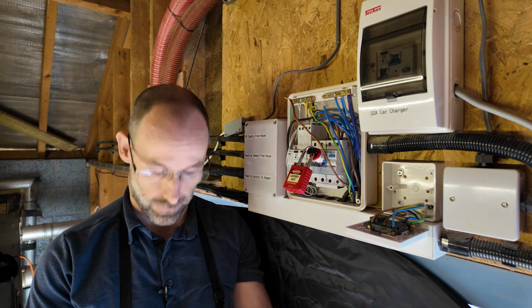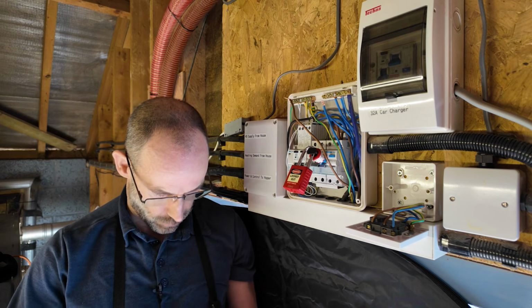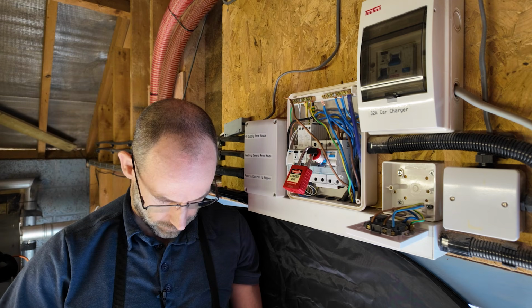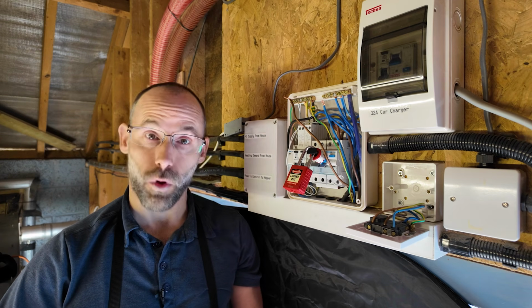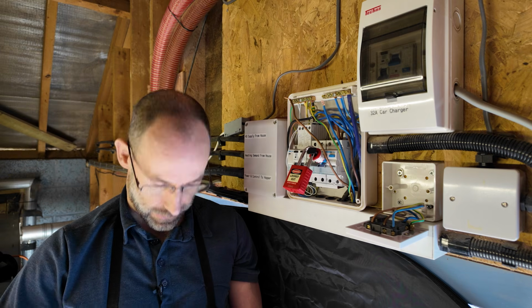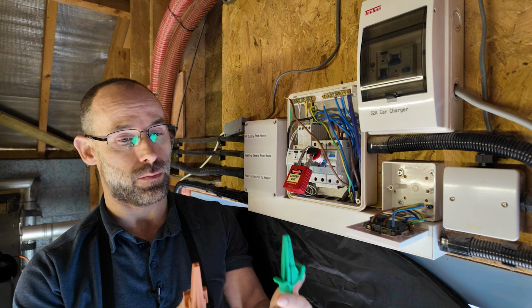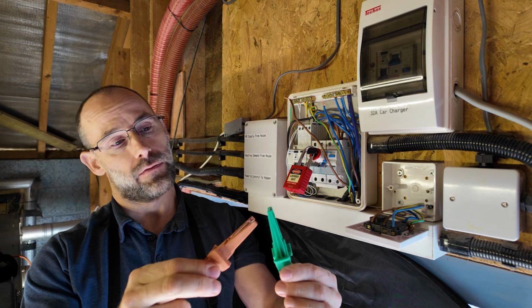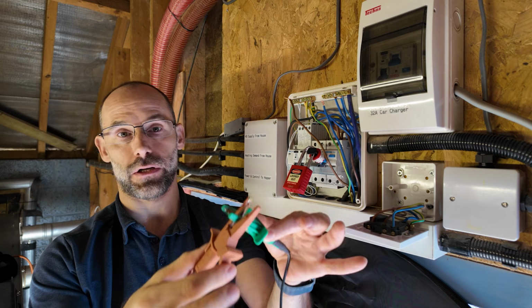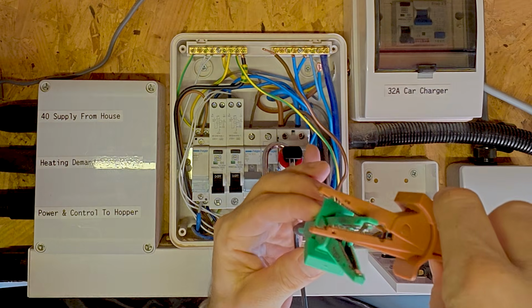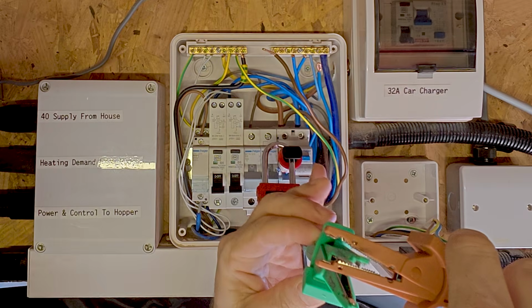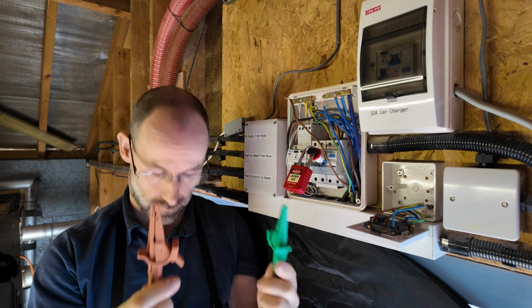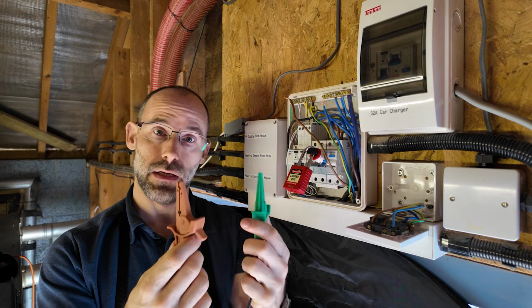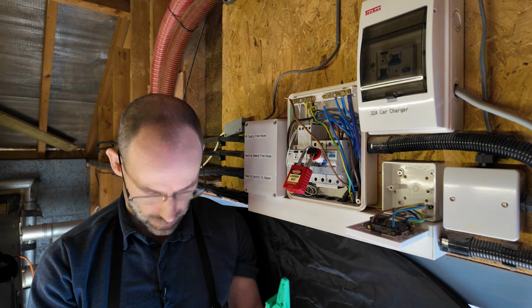The other thing you need, even if you rented one of these devices, is of course it's hard to rent the knowledge. That's called hiring an electrician, right? There's a lot of background knowledge going into what tests we do in what order and why, and particularly what you need to do if you find a curveball. All right, so this is set up now for insulation resistance testing. When I put these crocodile clips together, there is actually, you're not going to see it, a tiny little spark, which is always fun, because it's putting 500 volts between these clips. As I say, it's low energy, so I'm not putting myself at great risk here by doing this.